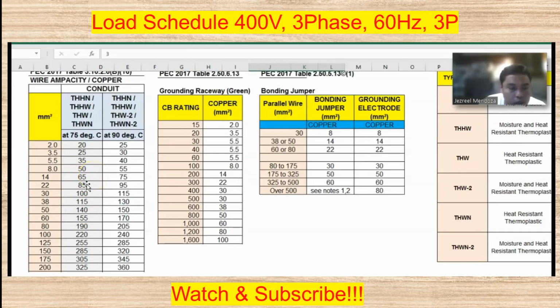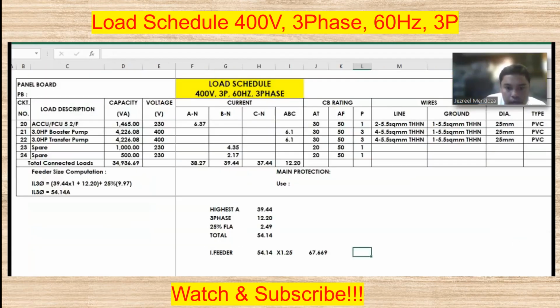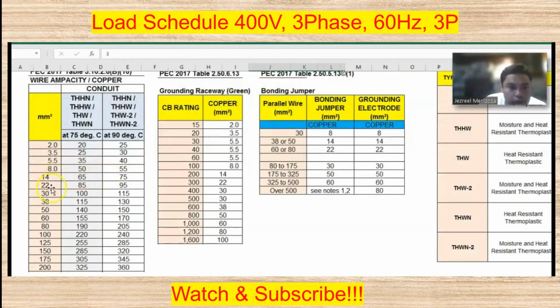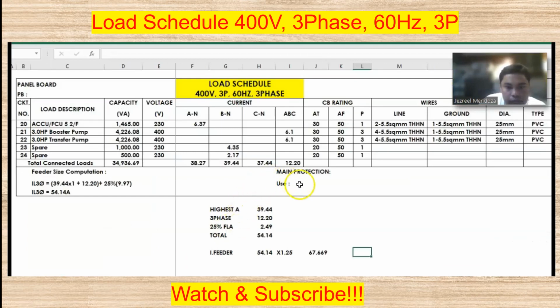If we use 22, that is 85, so exceed na tayo ng konti. Okay, from this we can use this 14 square mm. Okay, we have 4 wire, 14 square mm, and then THHN.